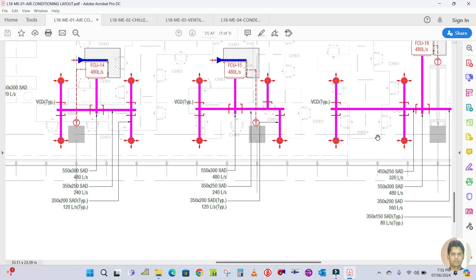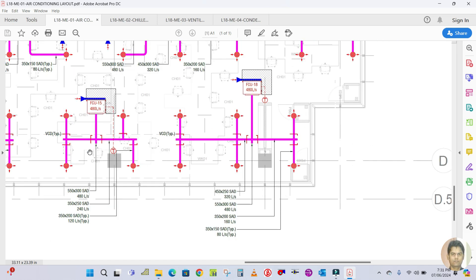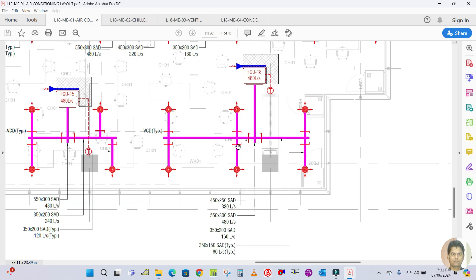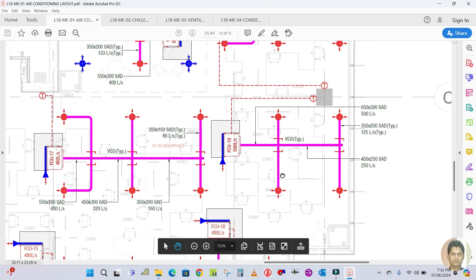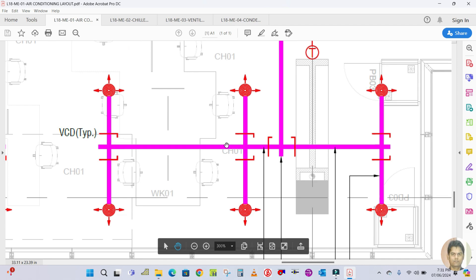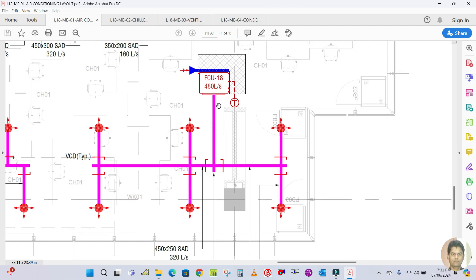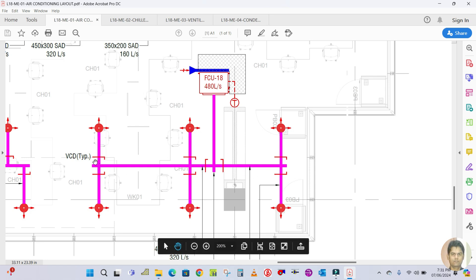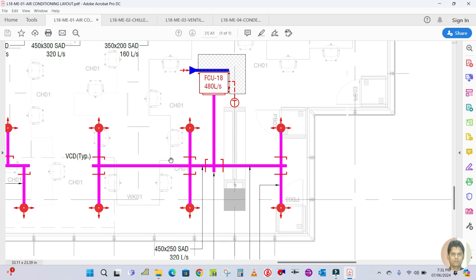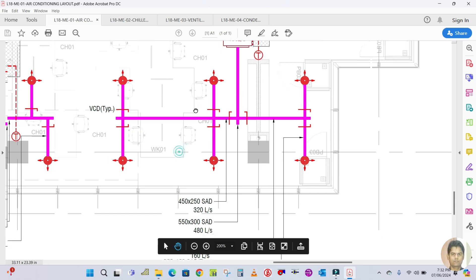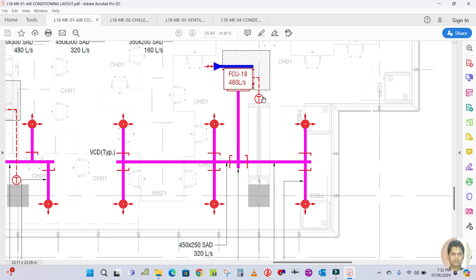All these designs are FCUs and are typical. For example, this is fan coil unit FCU-18, and the airflow rate for this FCU is 480 liters per second. This is a single-line diagram showing the ducting layout. There are six round diffusers connected to this fan coil unit. The L-type notation is showing the volume control damper, and this FCU is connected to a thermostat — 'T' stands for thermostat.